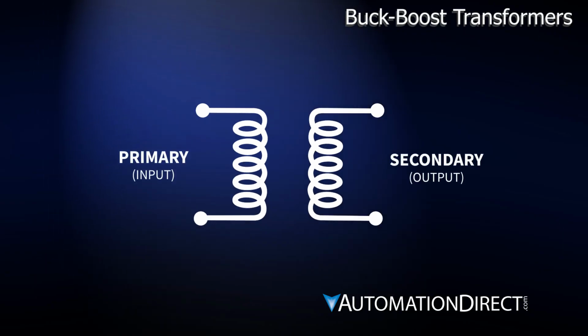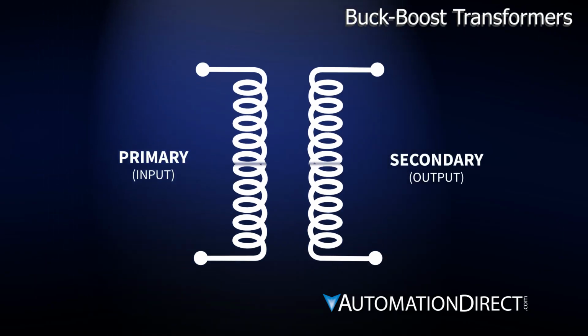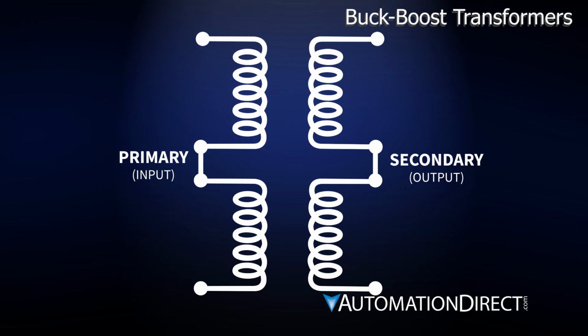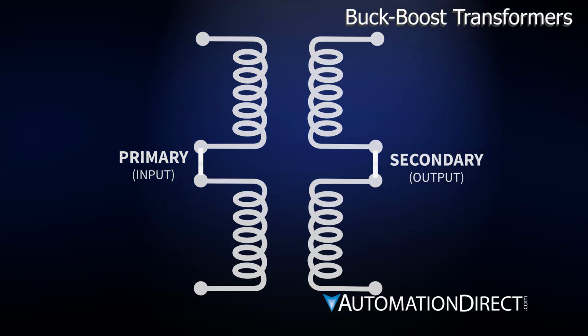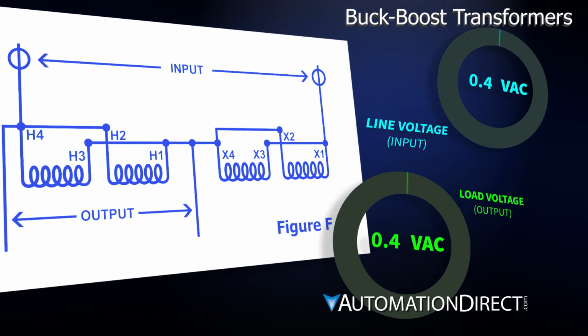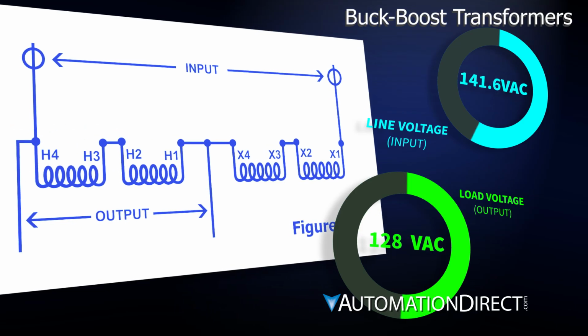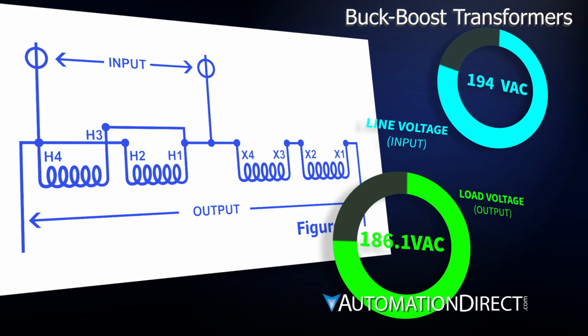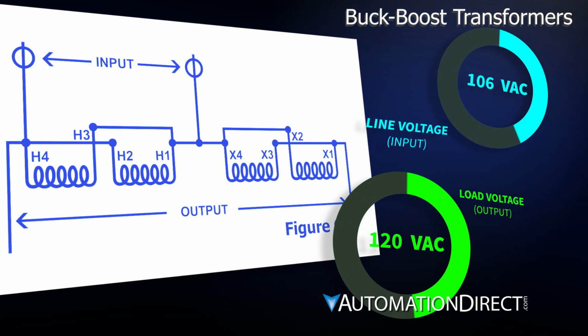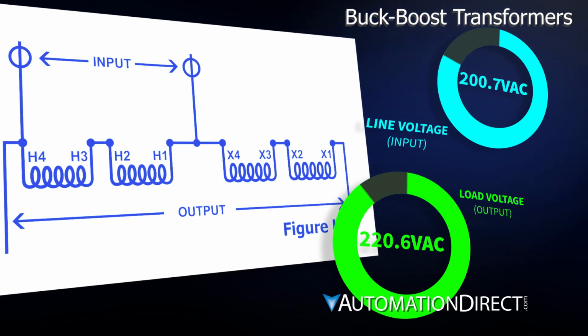Unlike standard isolated transformers, buck-boost transformers consist of 2 primary windings and 2 secondary windings. By connecting the windings in different ways, a buck-boost transformer can either add or subtract from the line voltage to achieve the desired output.